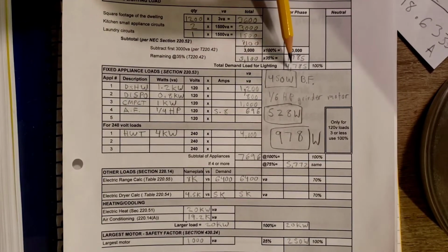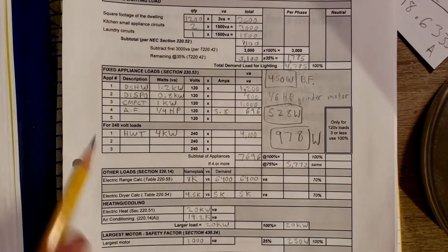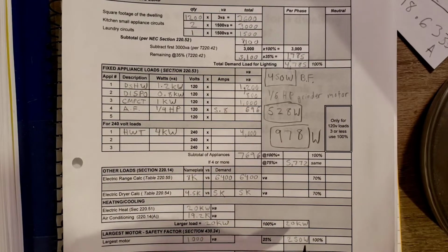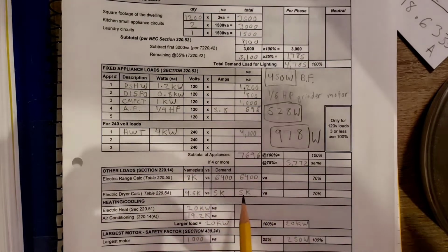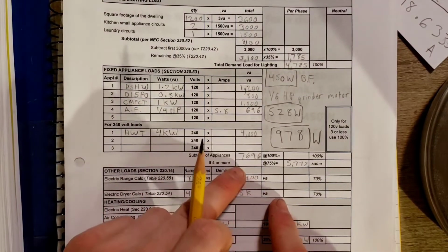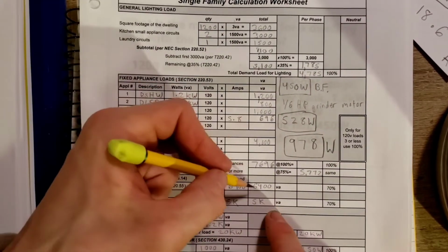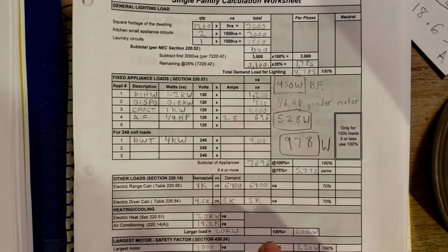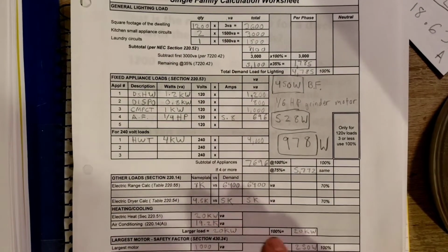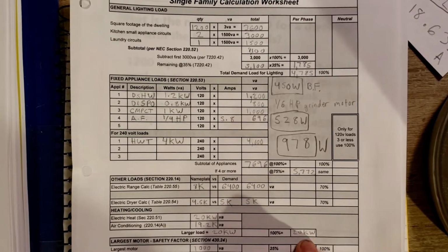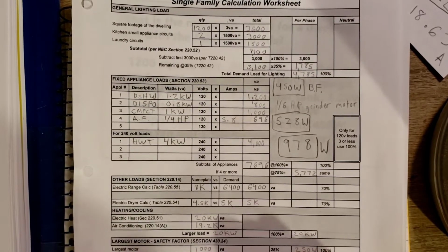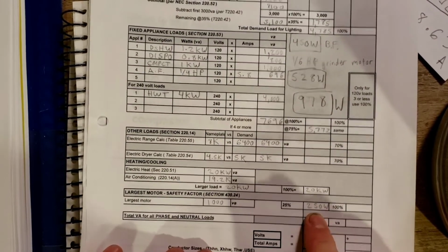And now we're going to get all of our totals, which is our total demand lighting load right here. Our appliance load here. And then we actually need to, both of these are finalized. So our range and our dryer, we're going to add those together too, 100%. And then since we chose our bigger one here, we're going to only choose the 20 kilowatts, the bigger one that we chose. And then we're also going to add what we just did, our largest motor, 25% of that. Okay, let's add it all together and see what we get.